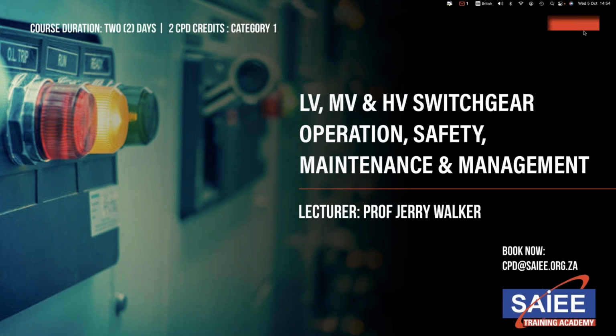It then follows with the different types of medium and high voltage circuit breakers and the methods applied for effective arc extinction. The requirements for switchgear to be certified as internal arc rated switchgear are also addressed, before finally looking at the role and application in coordination of protection systems, as well as the basic maintenance requirements of circuit breakers.